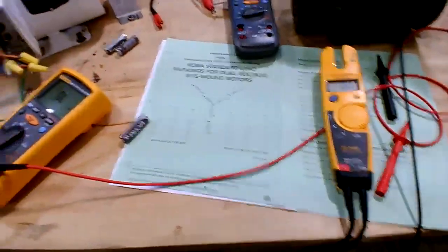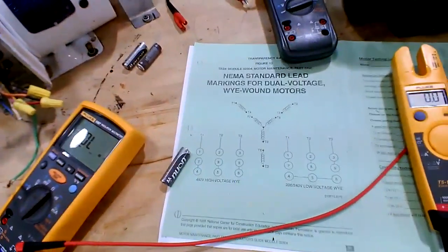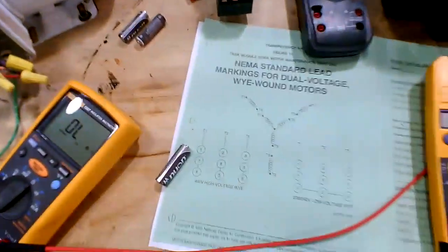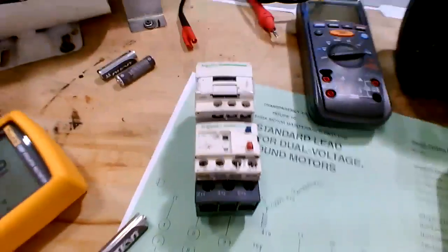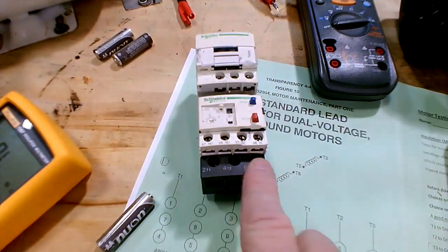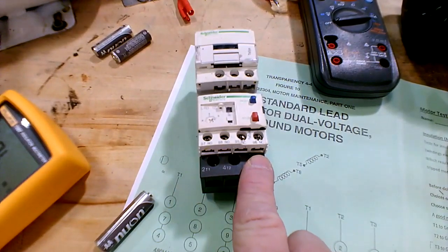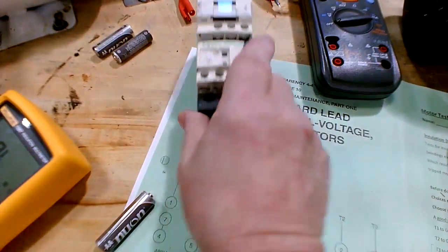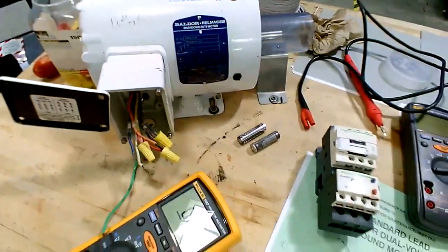If it reads good here, resistance-wise, but it doesn't at the original point, way over here for the wire, you've got something going on with the wire. You know what I mean? So you've got to consider that too, because the wire and the conduits are in the picture, and the windings in here. The symptom I would look for is if the voltages look good and they are balanced, but yet the currents are not, then you're looking at either wire problems or the windings going bad.